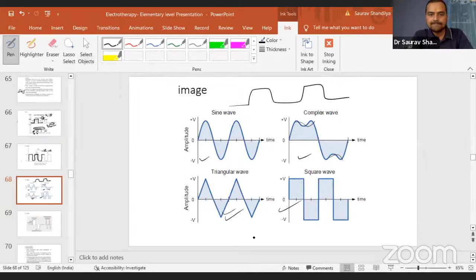So now this image is again very, very important for all of you. The reason is that it is a self-explanatory image. See, this is the amplitude, as I told you, from the baseline, how much it is going up, and again how much it is coming down from the zero baseline. This is called the amplitude. This is the pulse width, just now we saw. And what is pulse cycle? Pulse width plus the time when the current is not flowing, until you start the next pulse, is called the pulse cycle.